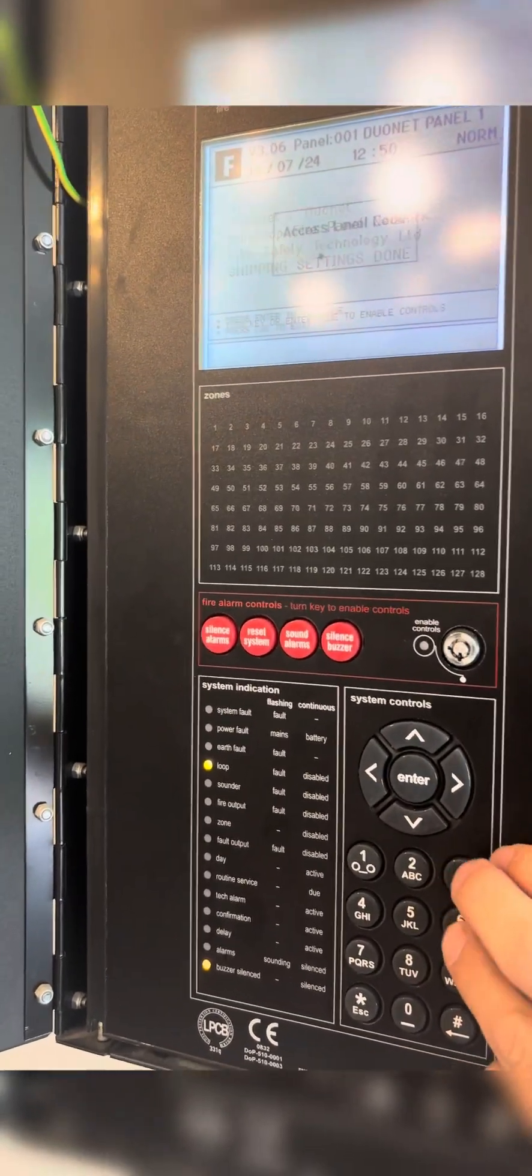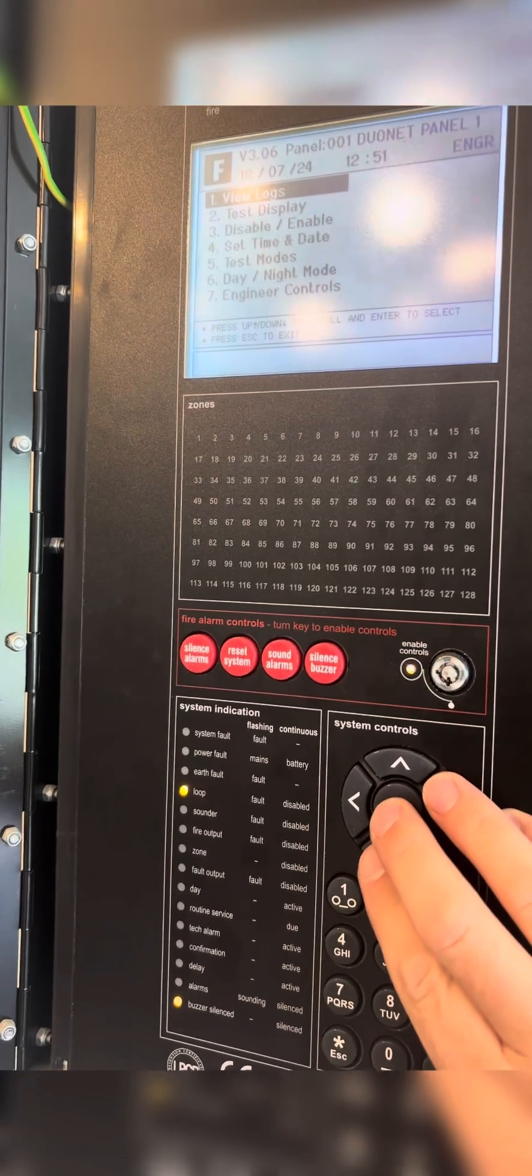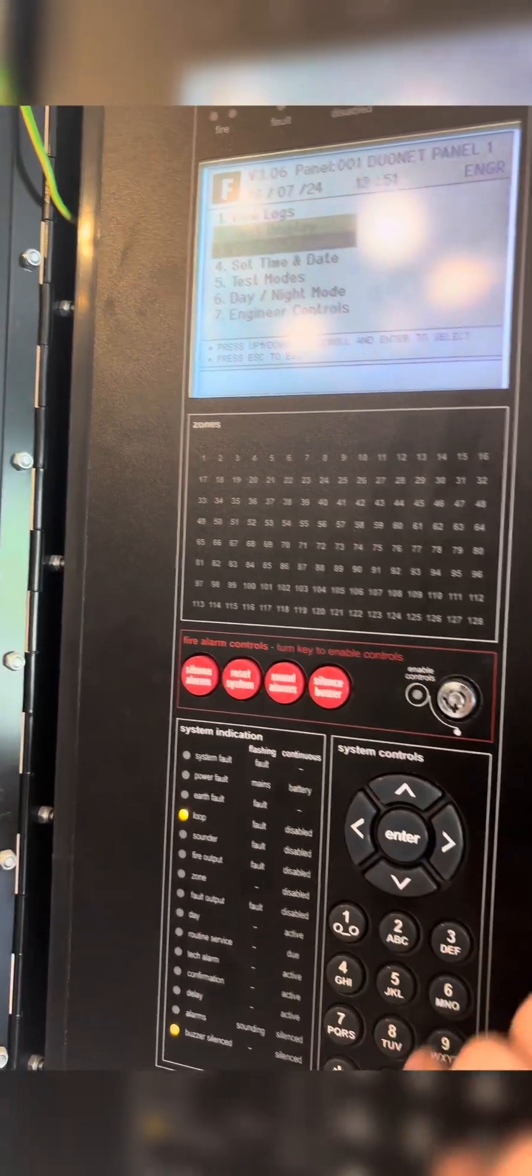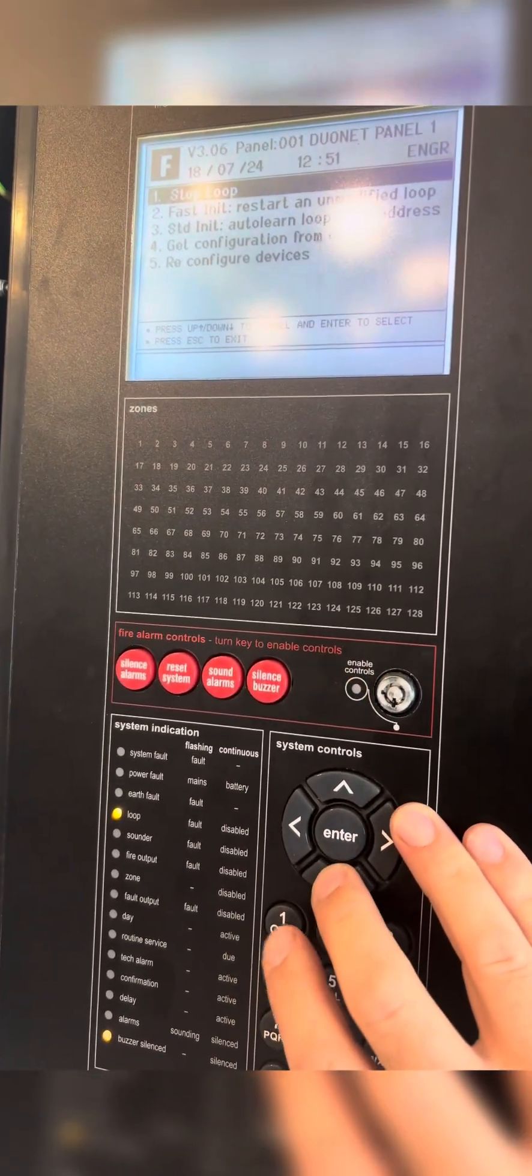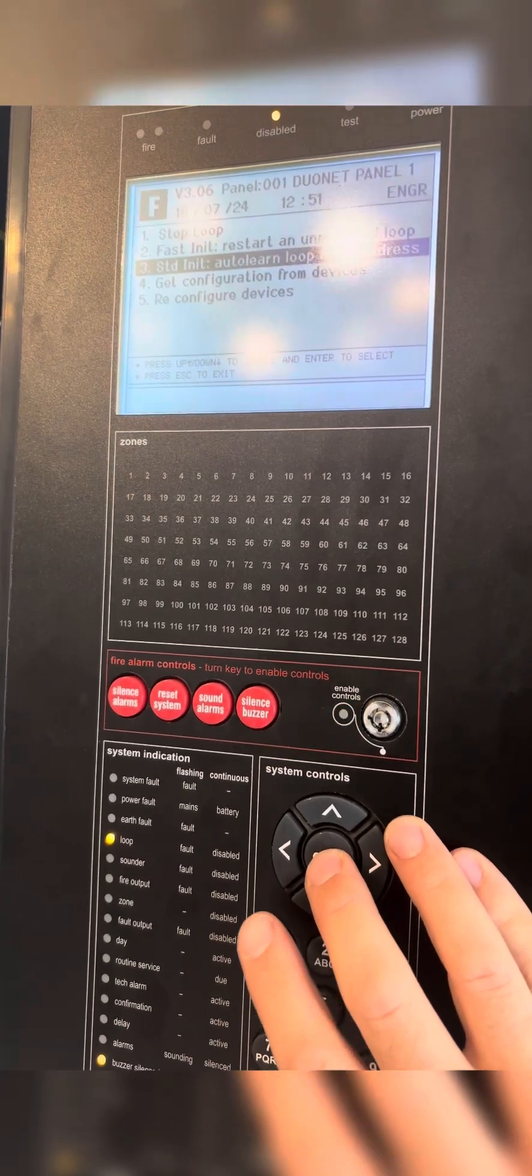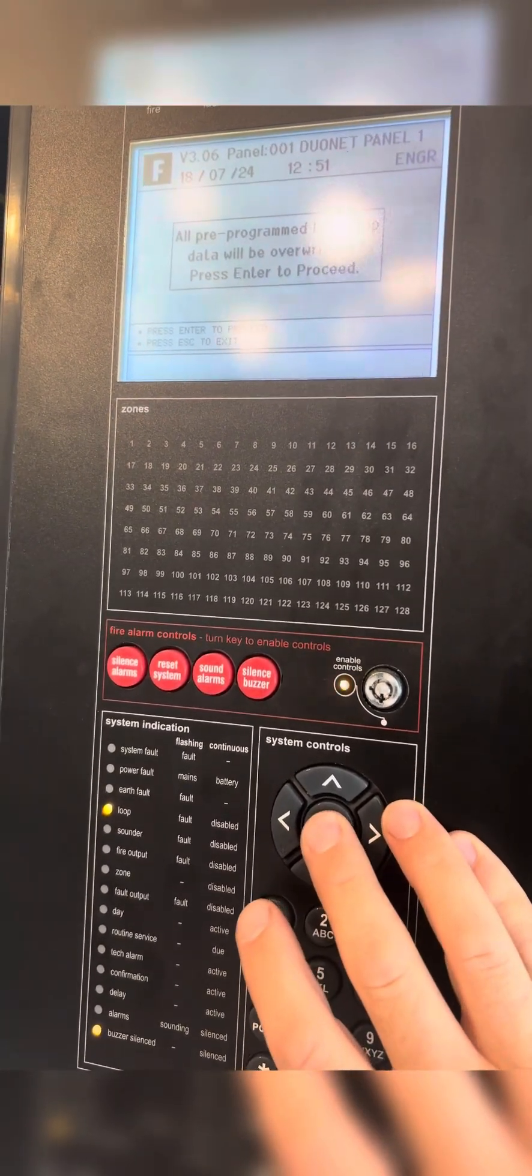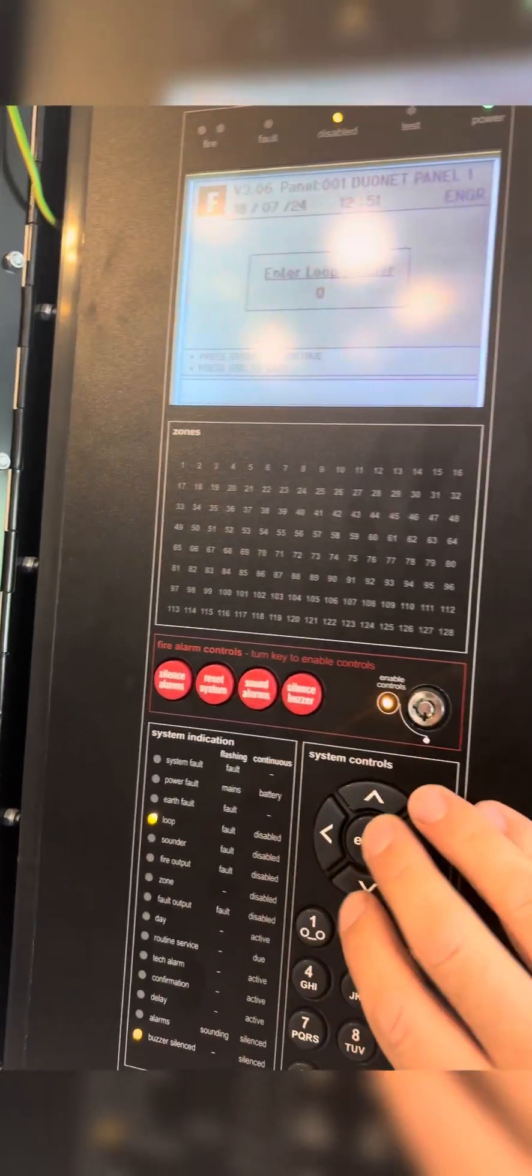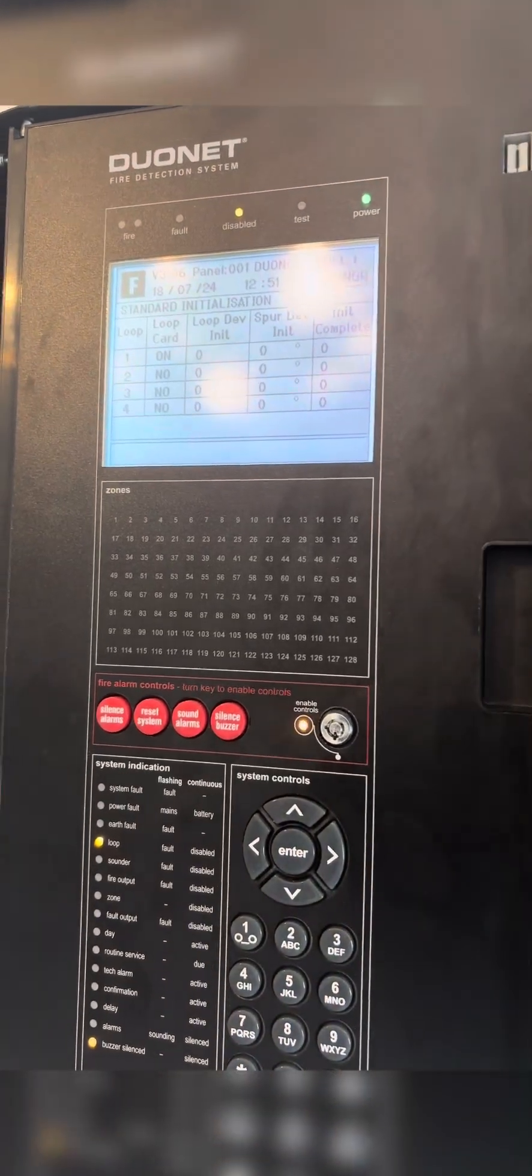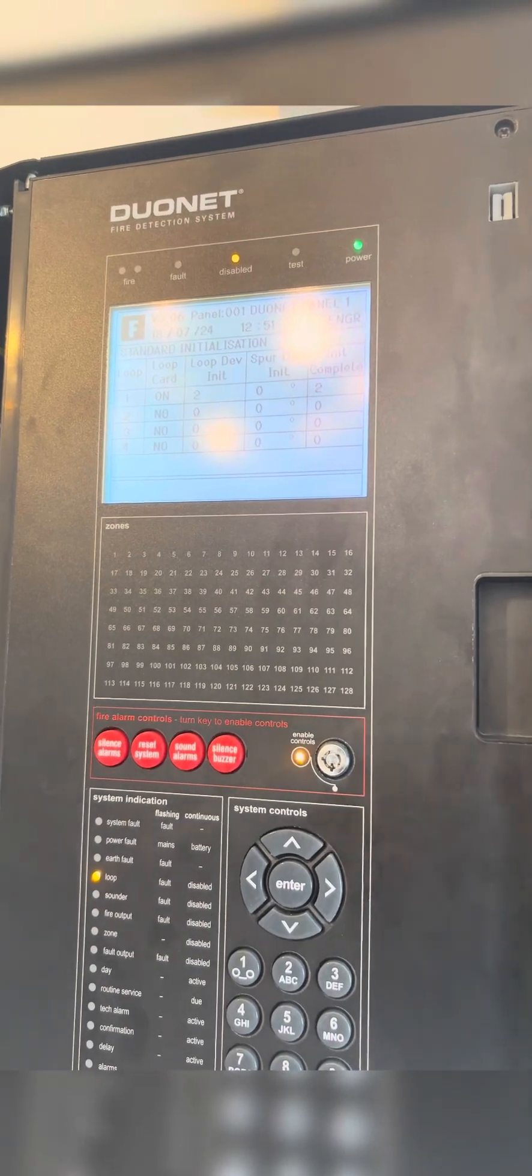Now we're going to reinitialize it. Type in our engineer code, go back down to Engineer Control, option number 7, and onto Loop Control. This time, go down to Standard Initialize Loop. Never go Fast Initialize—I don't know why, but they tell you never to do that. I stopped a single loop, so I'm going to start single loop. Type in my loop number, which was 1.